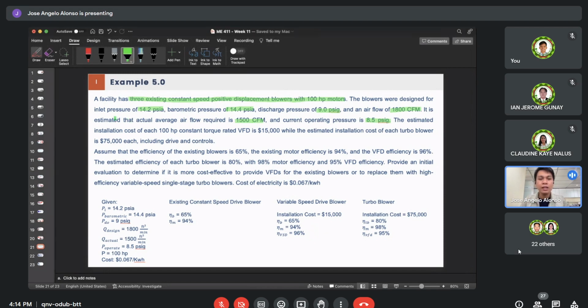Pero yung requirement lang pala, o yung actual average airflow lang naman na nire-require is just 1,500 CFM, meaning merong 300 CFM na over-provided ng ating fan na natatapon lang, na hindi nagagamit. Okay? So, those wastage equate to cost of operation, sa electrical cost ng ating motor. Kaya ang isang option dito, class, we are given 2 options here. Yung first option is to install a 100 HP constant torque rated VFD na nakakahalaga ng $15,000 ang installation cost.